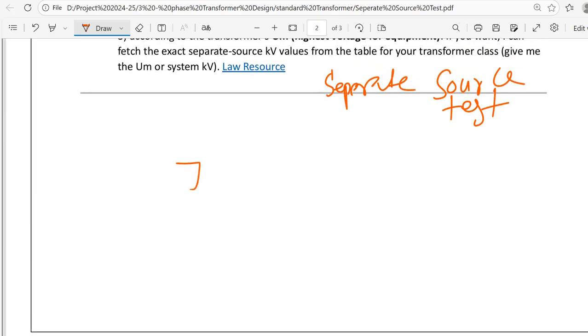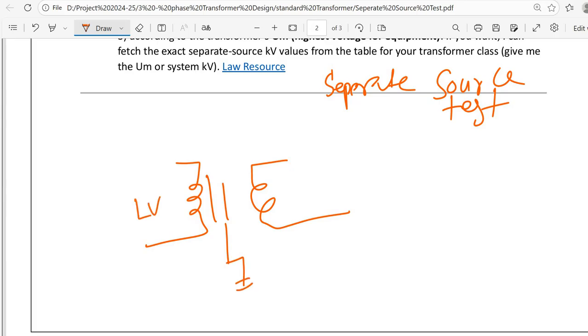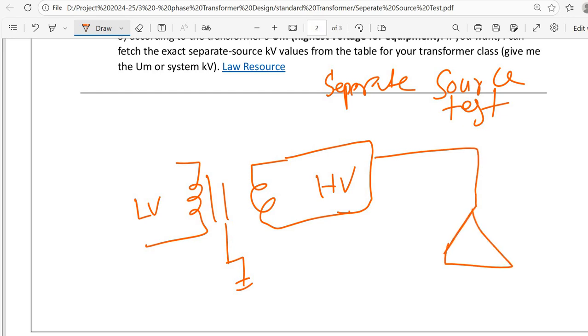So this is the transformer; this is the core ground, this is the LV, this is the HV. If you want to do the separate source test of HV, apply high voltage on the HV side, and the other windings are grounded and connected to the earth. This is the separate source test.